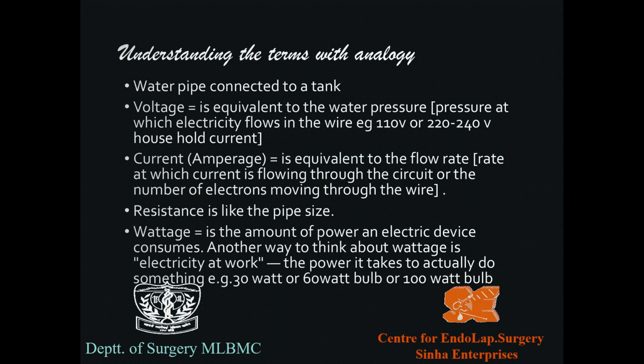Now, understanding these terms, we all know from our old knowledge of physics the watt, the volt, the ampere, and so on. But just to draw an analogy, a water pipe connected to a tank is basically a wire which is connected to the output, your electrosurgical unit. So what is the voltage? Voltage is equivalent to the water pressure at which the water is flowing. So here it is the pressure at which the electricity flows in the wire. That means 110 volts, 220, 240 volts. You regularly see on an appliance, you will read 220 volts only. Or you have one from the US, you will find 110 volts only. So we are basically talking about the pressure at which the electricity is going to flow inside the wire.